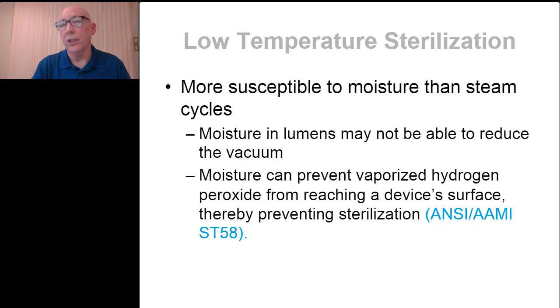Well, what about low temperature sterilization processes? Why do devices need to be dry going into the low temperature sterilizer? Well, the presence of moisture in the lumens, for instance, could lead to aborted loads because that low temperature sterilizer may not be able to pull as low a vacuum as is necessary for that cycle to continue, which will cause delays in the process itself and additional costs. You may have to cancel the cycle when it aborts and then start over again. So we want to make sure that even for the low temperature sterilizers, devices are dry. And again, refer to AAMI ST58. It gives you a lot of information relative to low temperature sterilization processing, and why devices need to be dry throughout that process as well.